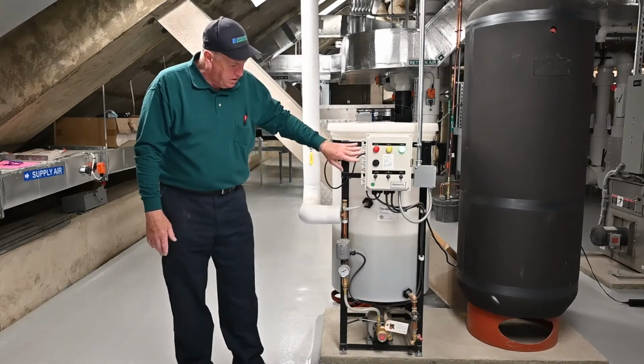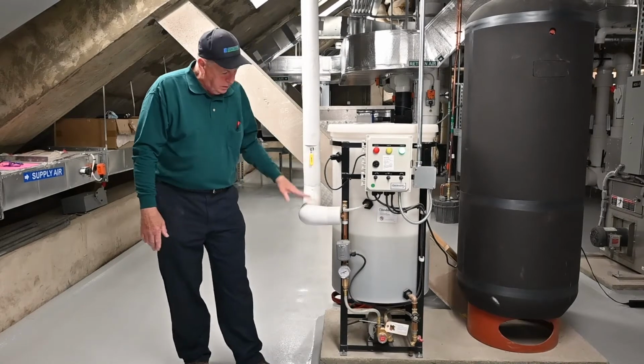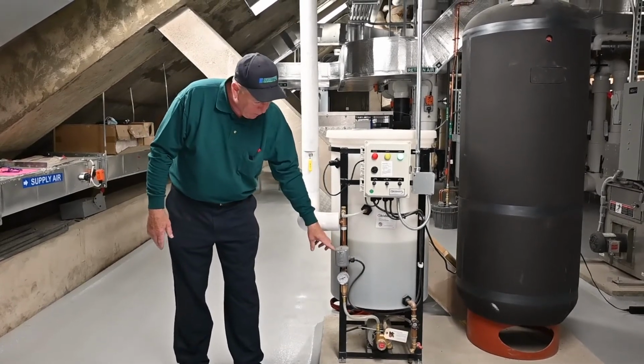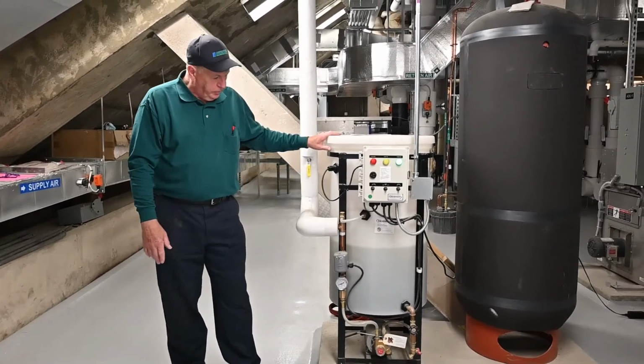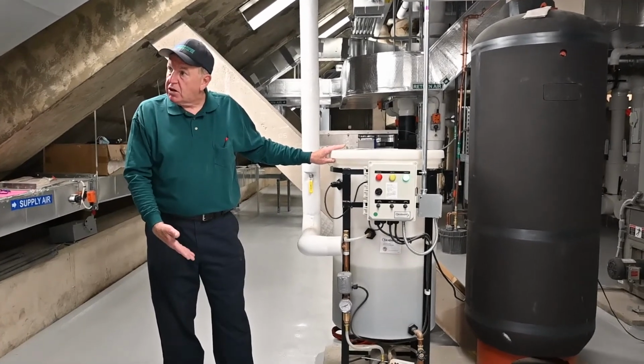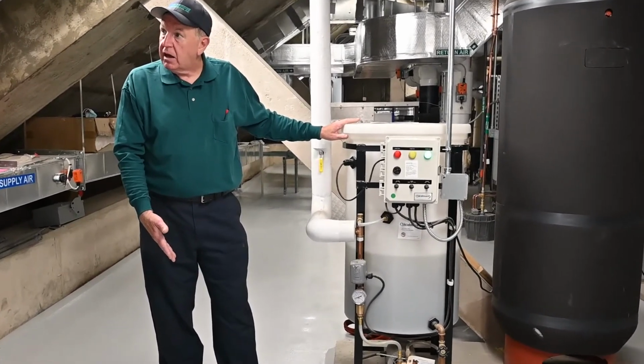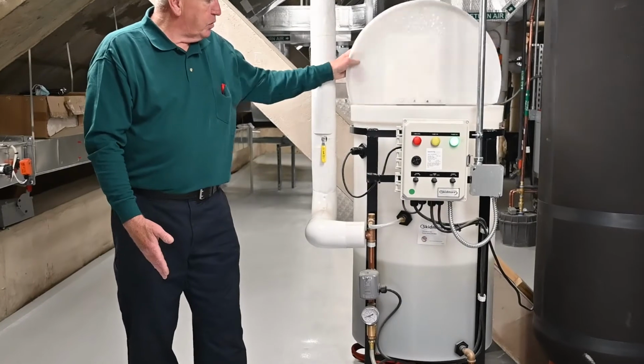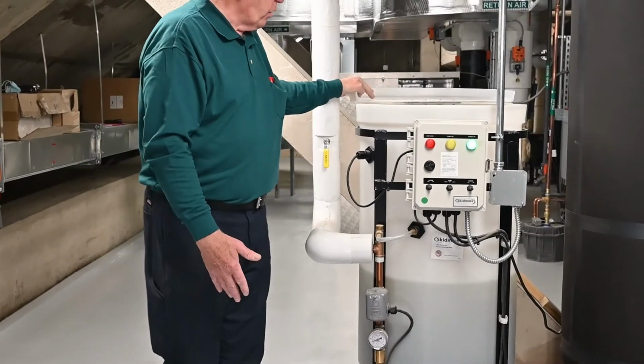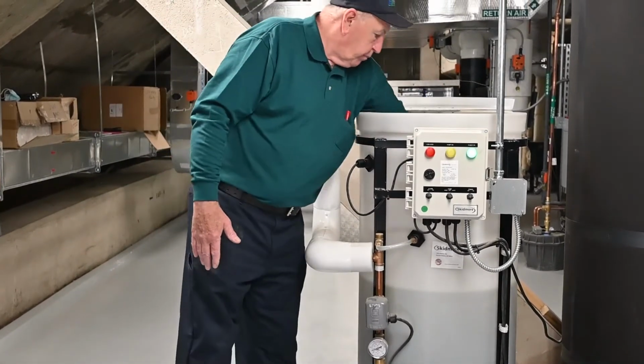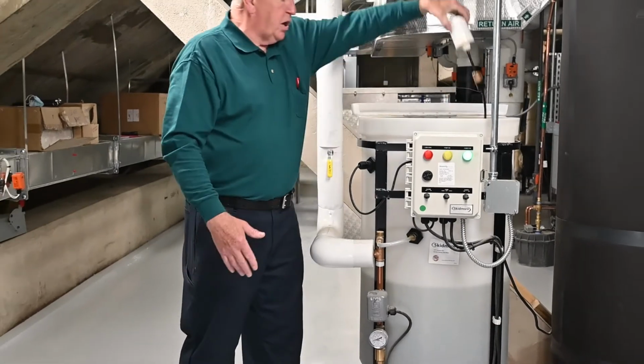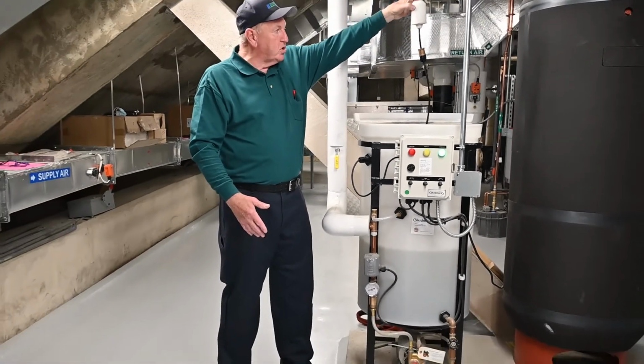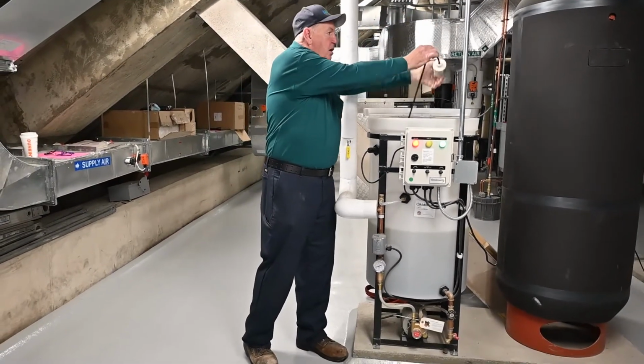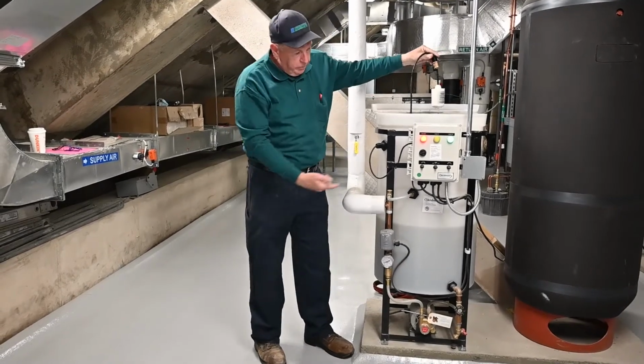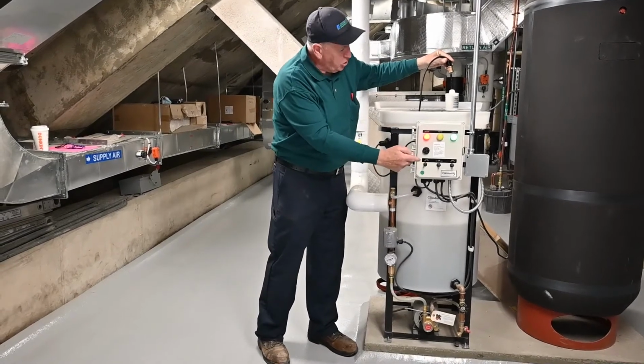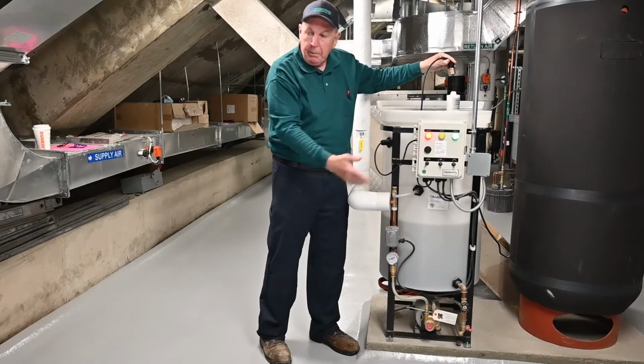So what happens is, if this pressure drops, the pump comes on, provided there's fluid in the tank. If there's no fluid in the tank, then the pump won't run, and you'll have an alarm. So there's a float switch in here, a tethered float switch that floats. If there's nothing in the tank, you'll get an alarm. Now you can shut the alarm off, but the pump won't run.